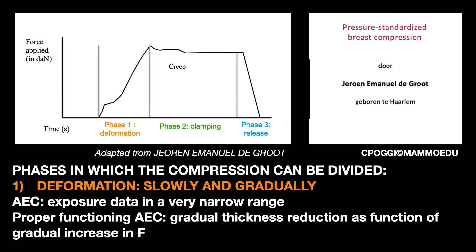Both the first and the second phase of the compression cycle are critical for the production of high-quality mammograms. The first phase has to be implemented slowly and gradually. My advice is therefore not to use the jump technique — pressing on the paddle several times until reaching the value you want — but rather holding it down continuously and lightly. If you go too fast, there may be an opposite reaction to the force exerted, called creep. The main reason for adopting a gradual approach is that FFDM systems are based on automatic exposure control, and the exposure data required to produce a high-quality mammogram fall within a very narrow range. These systems include thickness, and they work well when the thickness reduction is gradual as a function of an equally gradual increase in the applied force.